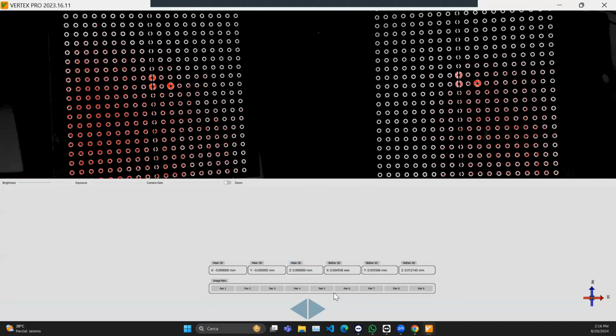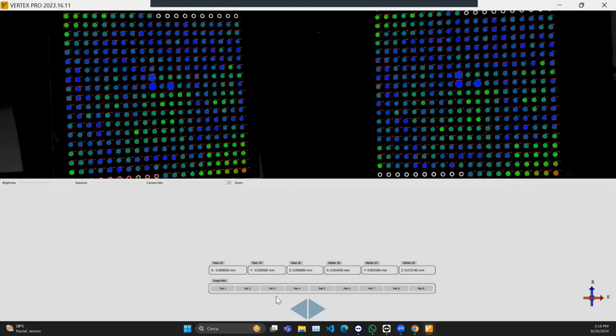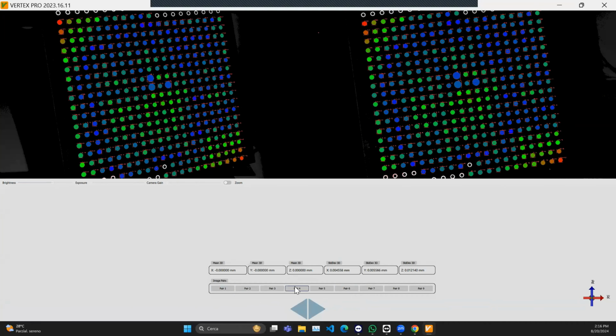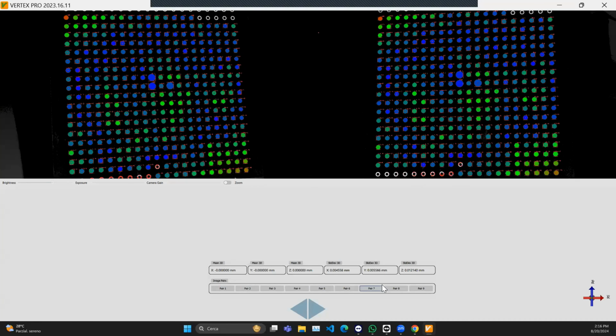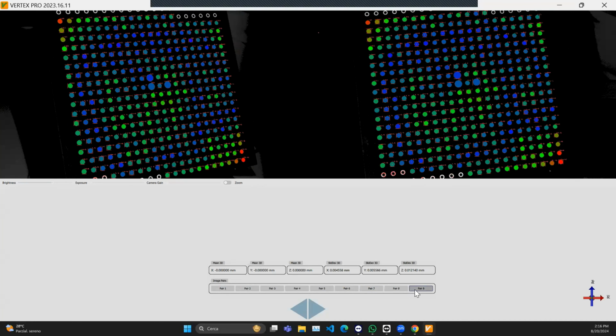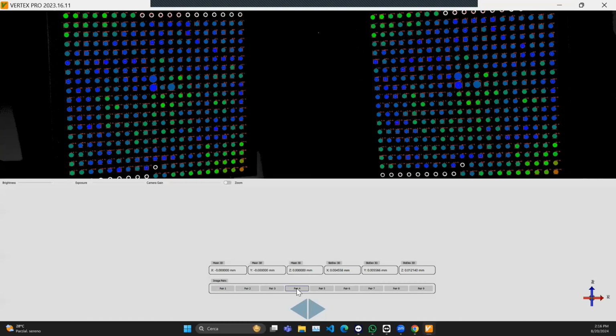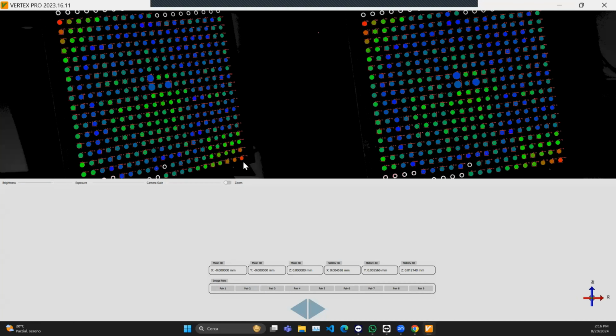If I click on check results here, I can see the distribution of the error for each image. I have to see blue and green. Blue-green means error very, very close to 0. Green means a few microns. Red means more than a few microns, but red at the boundary, and only in a few images, is allowed. The important parameter is what I read here: the standard deviation measured on the Z component has to be less than 20 microns for this configuration. When I'm at this number, I'm good. If we go next, we confirm the calibration. If we go previous, we cancel the calibration.